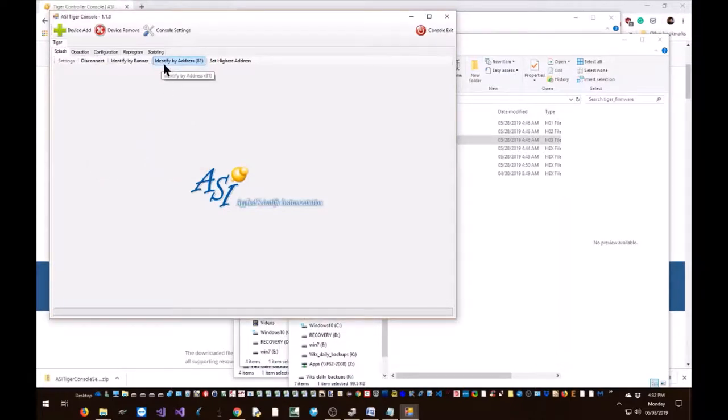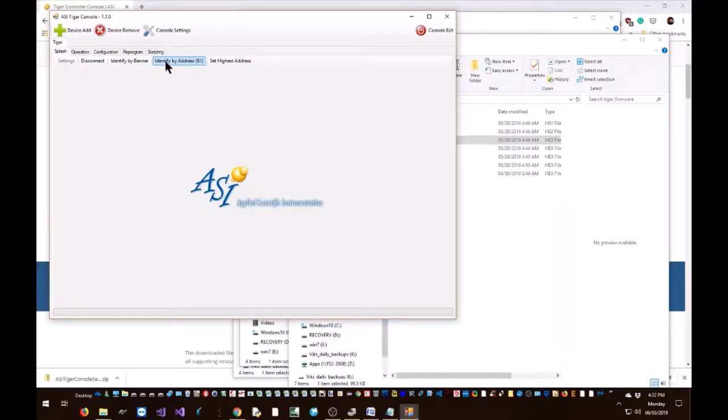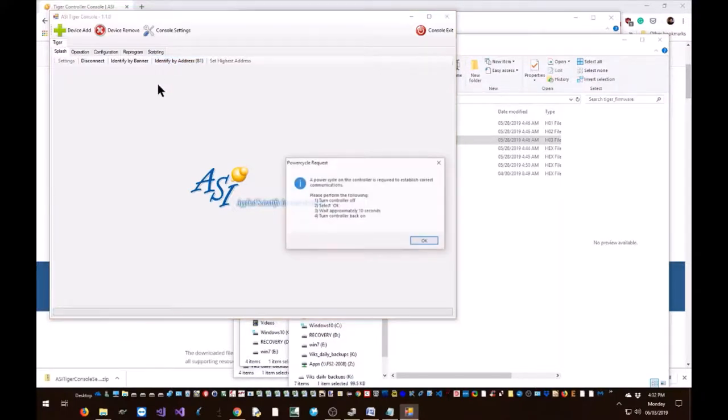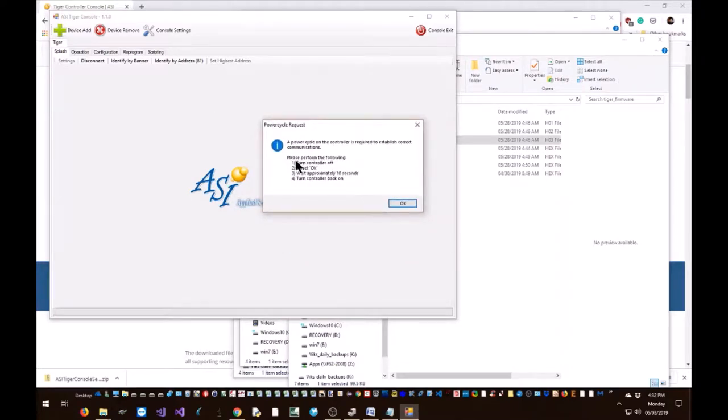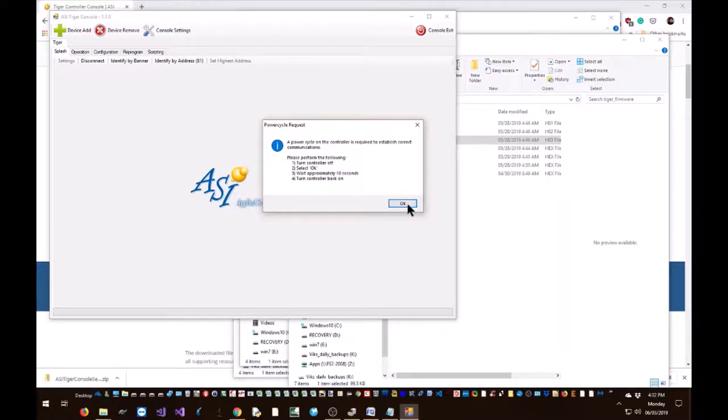Now the Tiger console will look for all the cards that can be present in a Tiger controller. Next, hit identify by address button. The Tiger controller needs to be on for this step. A message is shown: a power cycle on the controller is required to establish correct communications. Please perform the following step: turn off the controller, select the OK button, wait approximately 10 seconds and then turn the controller back on.